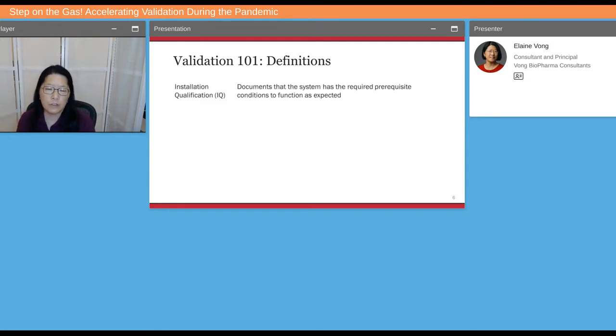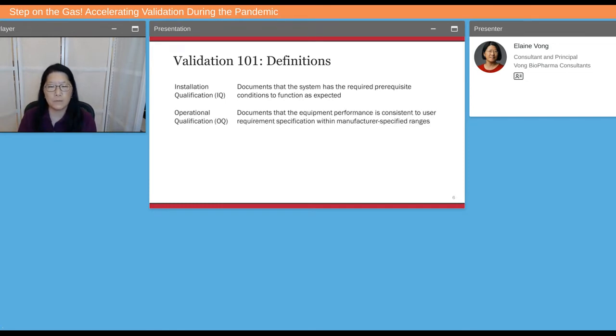Validation 101 definitions. IQ is the document that the system has the required prerequisite conditions to function as expected. OQ documents that the equipment performance is consistent with the user requirement specification within the manufacturer-specified ranges. Sometimes people will ask, what if I never intend to operate at the manufacturer's limits of the equipment? This is a soft requirement.